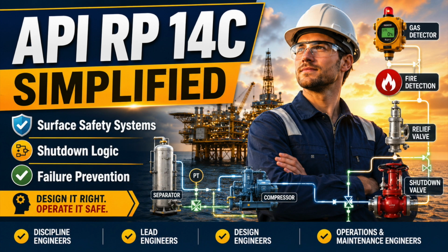Normal process control must also remain separate from safety thinking. A level controller is designed to maintain the operating level, but a high-level shutdown exists because the controller, transmitter, valve, actuator, utility supply, or operator intervention can fail. A pressure controller maintains process pressure, but a high-pressure trip exists because outlets can block, upstream conditions can change, control valves can fail, and downstream pressure can increase.